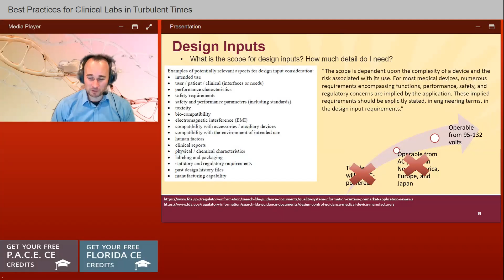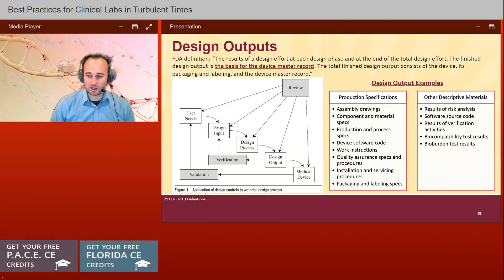So examples could be assembly drawings, production and process specs. It could be a piece of device software code that's analyzing some fluorescent signals, for example, and then verifying that I met the design inputs. It could be packaging and labeling specifications, the results of a risk analysis, biocompatibility test results, verification activities. These are all outputs that verify my inputs are being met.